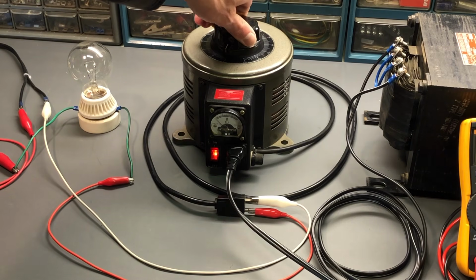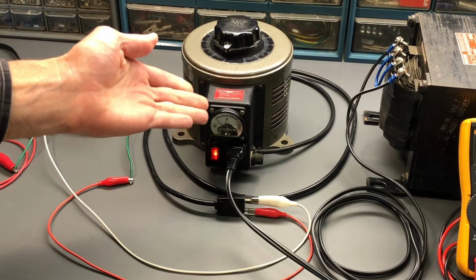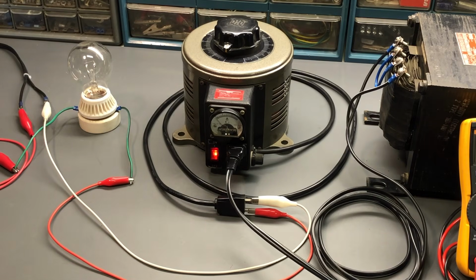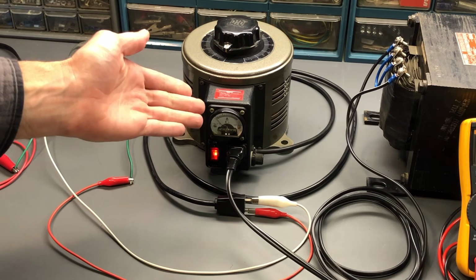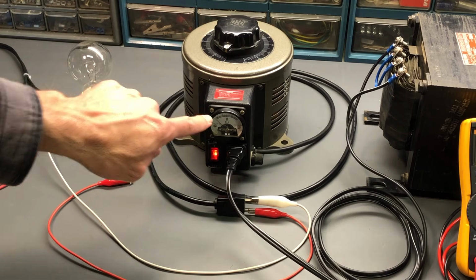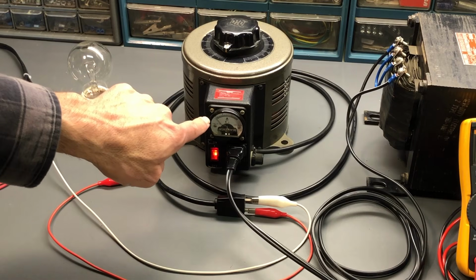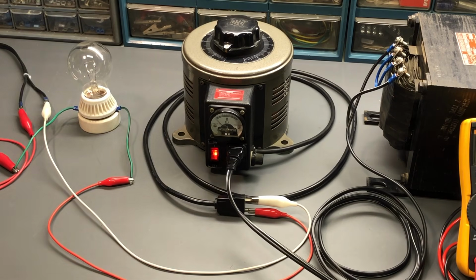All right, and if I bring this back down again, you can see that jumpy high current that we were getting initially is not there when there's no load. So if you had no load or very light load, you wouldn't have that effect. But a heavy load or a short circuit on the output causes a lot of fluctuation and a lot of heavy current to flow initially. All right. So we'll move on to the second configuration, and I'll reposition everything and get that set up, and I'll be back.